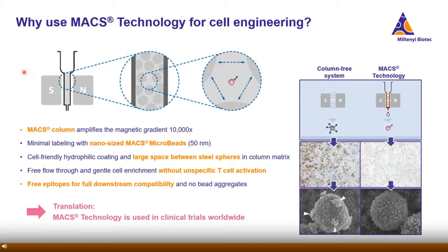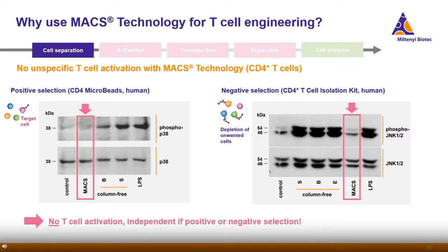Why is it so beneficial to use MACS technology for immune cell manufacturing? Our technology is based on MACS columns. Through the columns, the magnetic field is amplified 10,000-fold. This allows us to reduce the number of beads for enrichment and leads to minimal labeling of the cells. Further, there is a large space between the steel spheres of the column matrix that enables a free flow-through of non-labeled cells and enrichment of minimally labeled cells without unspecific cell activation.